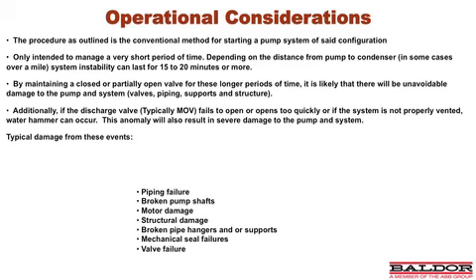Additionally, if the discharge valve, typically an MOV, fails to open or opens too quickly, the system will not be properly ventilated, resulting in water hammer. This anomaly will also result in severe damage to the pump and system.